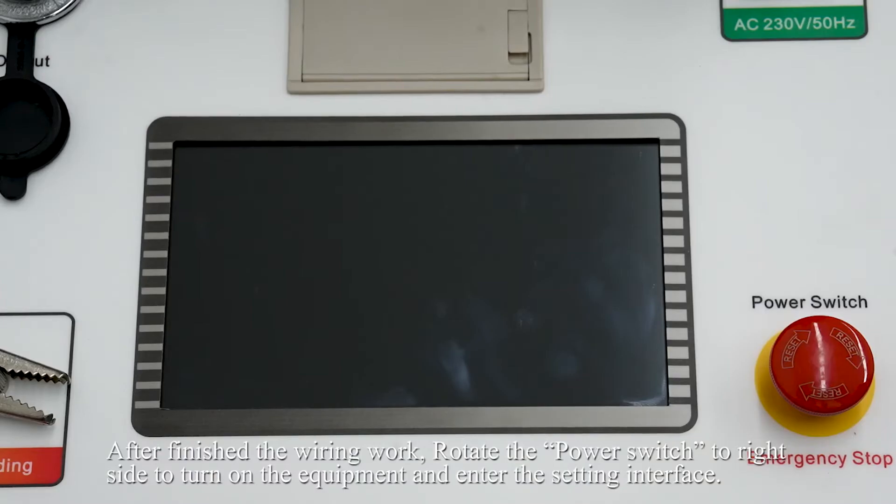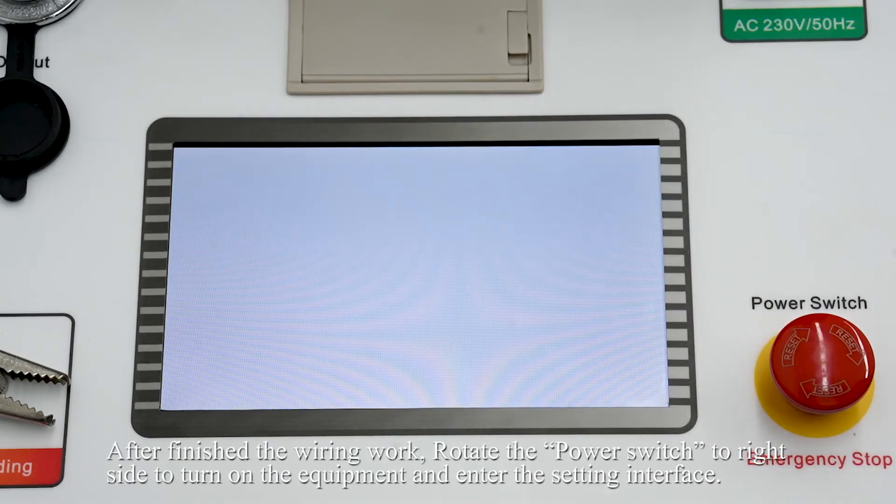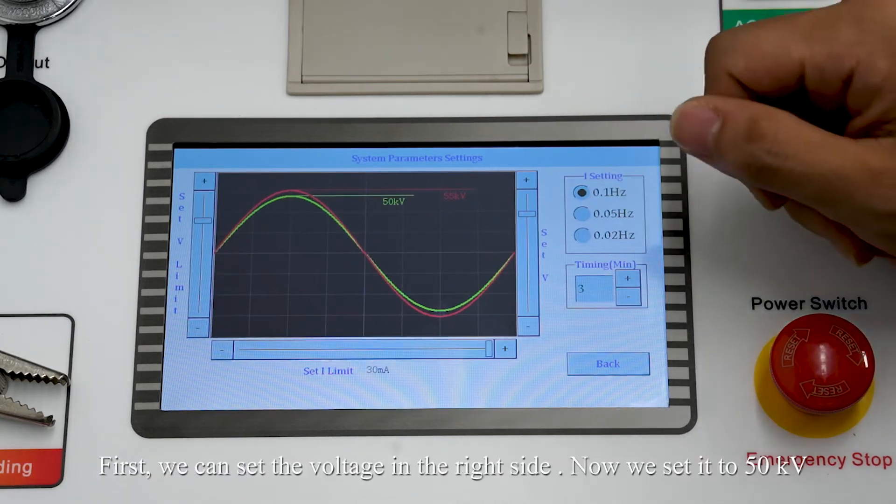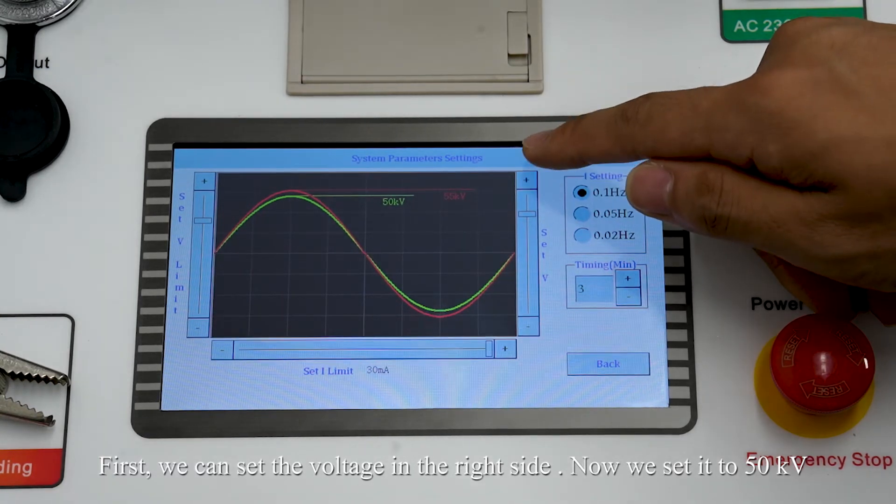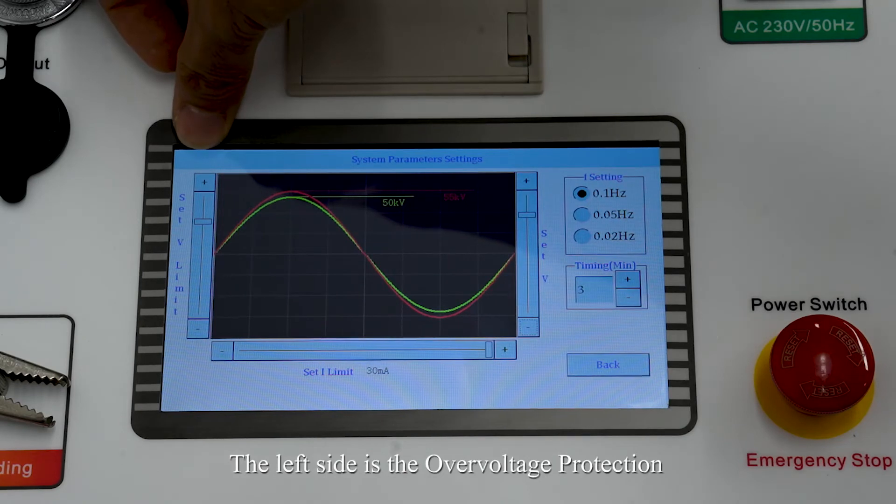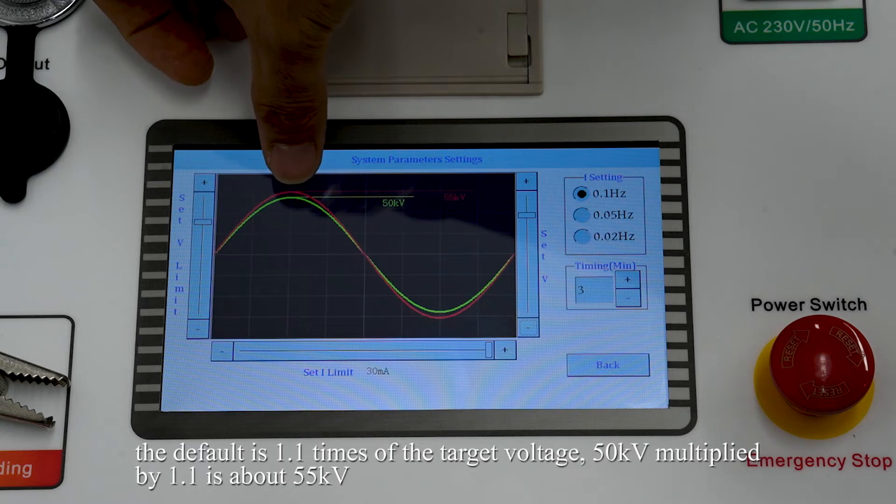After finishing the wiring work, rotate the power switch to right side to turn on the equipment and enter the setting interface. First, we can set the voltage on the right side. Now we set it to 50 kV. The left side is the over-voltage protection. The default is 1.1 times of the target voltage. 50 kV multiplied by 1.1 is about 55 kV.